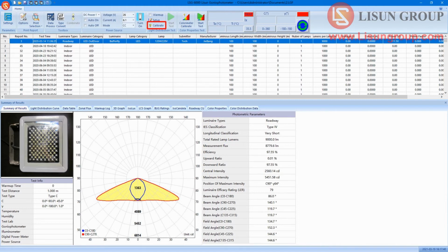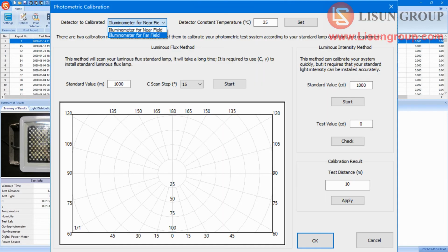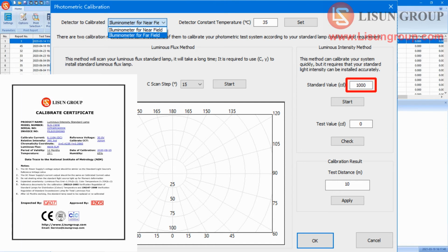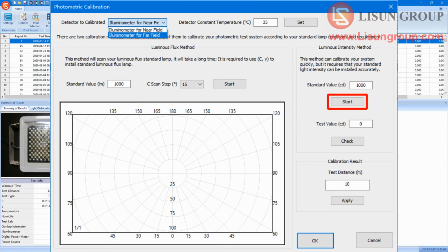Click Photometric Calibration. Choose Illuminometer for near field. We use candela calibration but not lumen calibration. Input the candela here. Click Start. Then the test distance will change automatically according to your darkroom size. Then click Apply and OK.